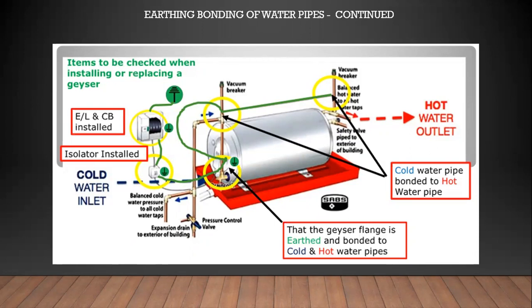Often you will find people use Surfix wire, the round metal stiffening wire, to wire the geysers, and they use that earth for bonding, and that's not correct. In a 2.5 millimeter Surfix, the actual earth wire is 1.5 millimeter. So that's also not according to the regulations.